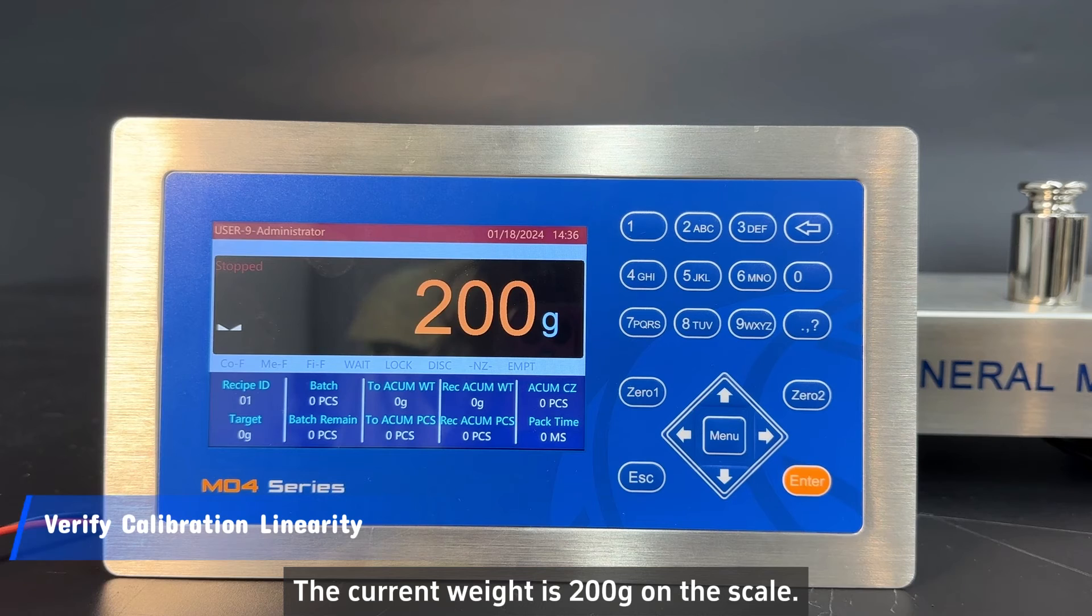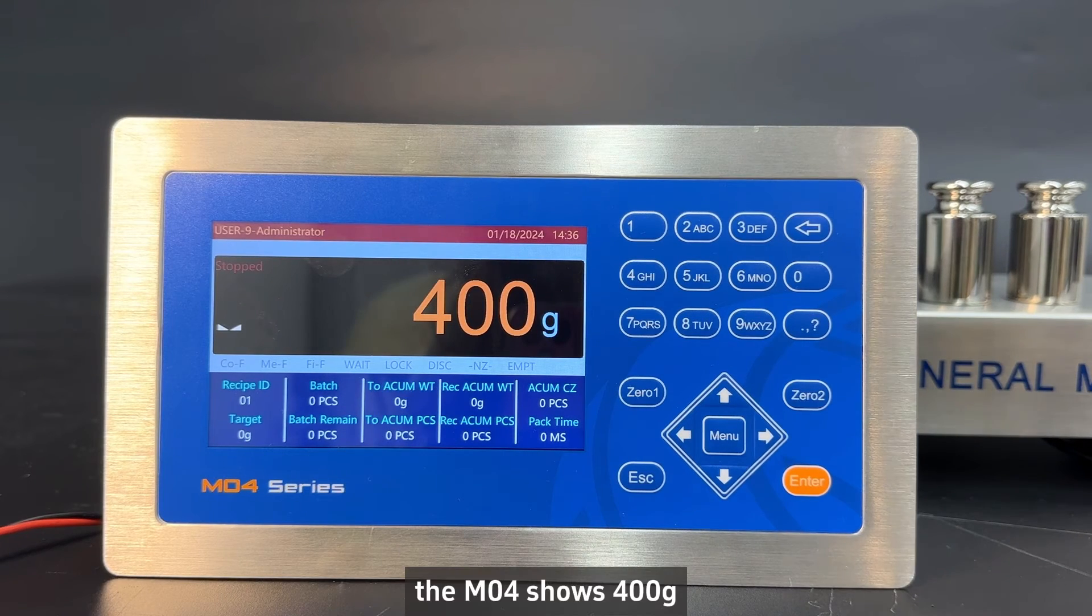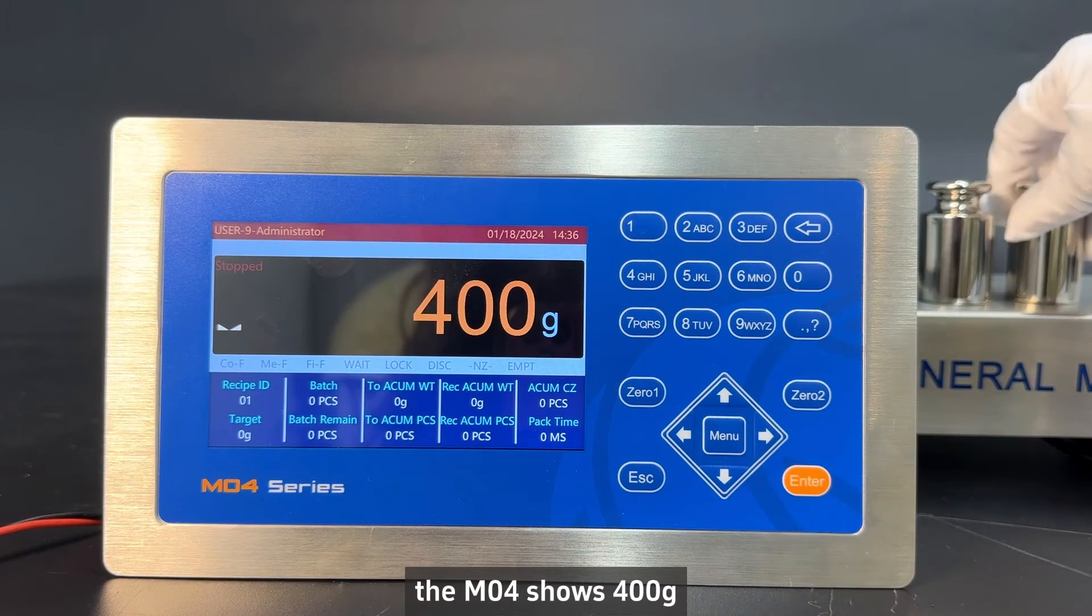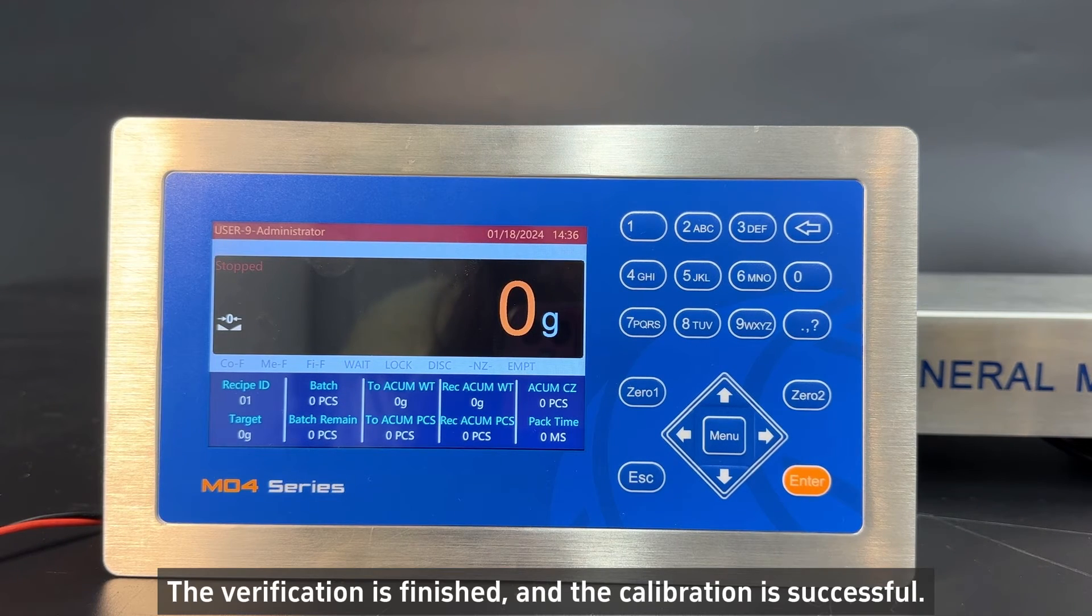The current weight is 200 gram on the scale. Put on another 200 gram weights. The M04 shows 400 gram. Remove all weights. It displays zero gram, which conforms to reality. The verification is finished, and the calibration is successful.